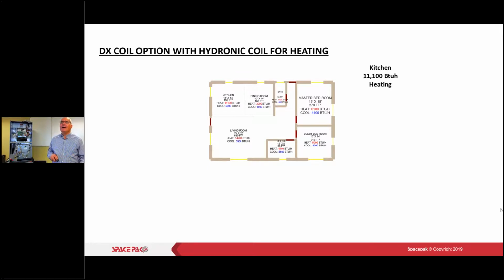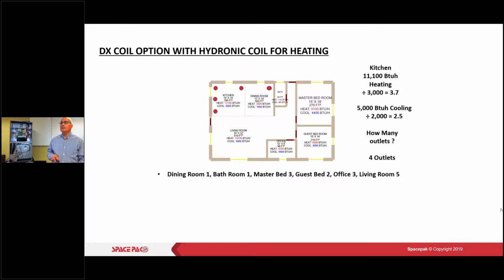All right. So same job here with a hydronic coil for heating. So there's the BTUs per kitchen. It's 3.7 outlets, so that's going to be 4. There's my BTUs for cooling. It's 2.5, so that's going to be 4 outlets. And again, we do that on a room by room basis, is what you're seeing here.